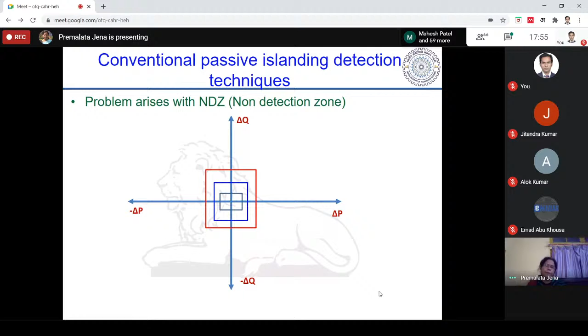This is known as the non-detection zone. As I said before, if your delta P, delta Q percentage power mismatch decreases, like 1%, 2%, 3%, it is increasing. If it is zero completely, then the technique may fail. So from there the research takes place. What could be our possible technique which will overcome this percentage of mismatch, even if it is very low or zero, that can also detect my islanding scenario? That is the meaning of this box.